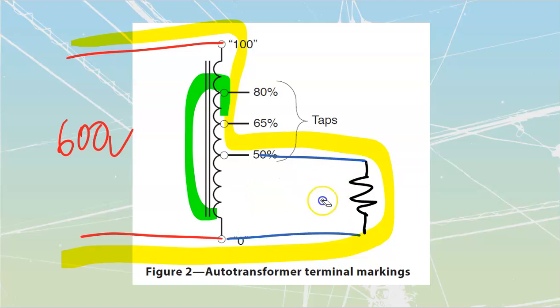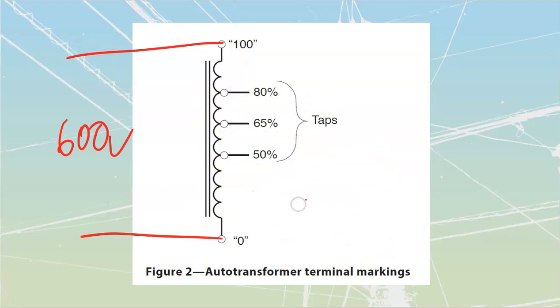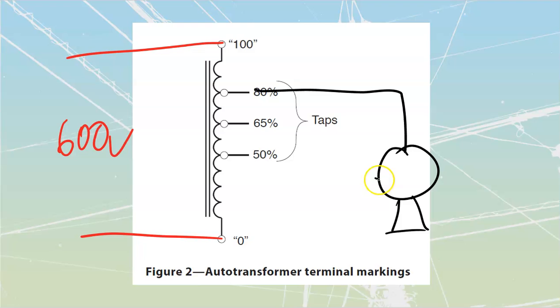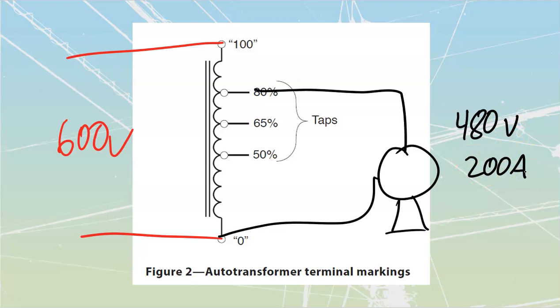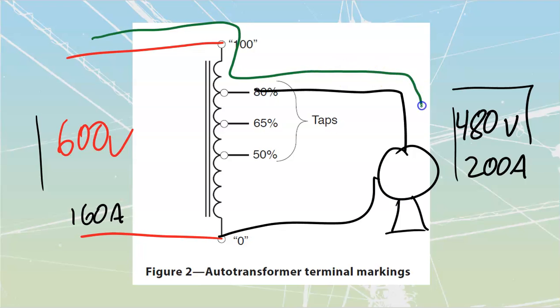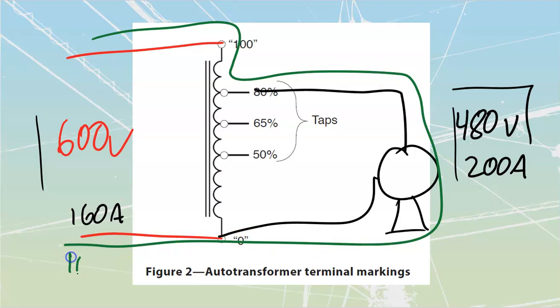let me just erase some of these over here. If I were to use this setup on my motor, I will draw it over here just as a one line. There's my motor that is attached across the 80%. It's got 480 volts. It has 200 amps. And we have this kVA that has to be matched on this side with 160 amps. So 160 amps are going to travel through like that. It's going to be this value over here, 160. And if I take a look at the difference between 200 amps and 160, I see that that's going to be a value of 40 amps.